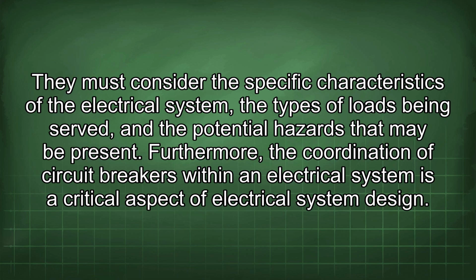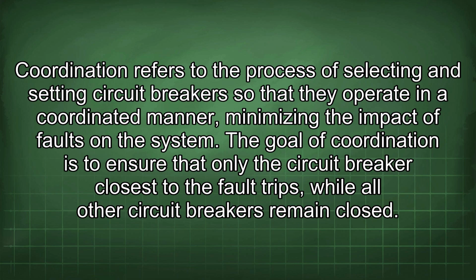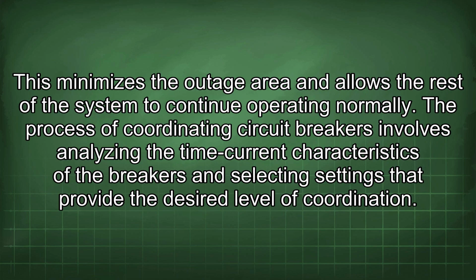Furthermore, the coordination of circuit breakers within an electrical system is a critical aspect of electrical system design. Coordination refers to the process of selecting and setting circuit breakers so that they operate in a coordinated manner, minimizing the impact of faults on the system. The goal of coordination is to ensure that only the circuit breaker closest to the fault trips, while all other circuit breakers remain closed. This minimizes the outage area and allows the rest of the system to continue operating normally. The process of coordinating circuit breakers involves analyzing the time current characteristics of the breakers and selecting settings that provide the desired level of coordination.